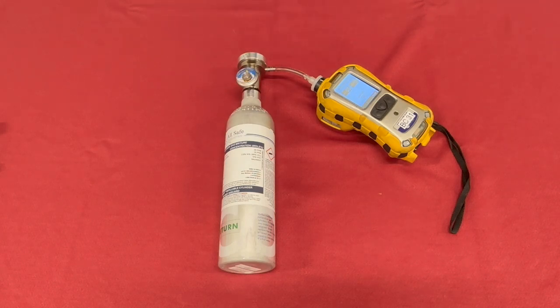Bump testing is not the same thing. All bump testing does is put the gas onto the meter, and once the meter is within 10% of the calibration gas, it says the sensors are working fine and I'm done, and it passes the sensor. If for some reason the sensor has drifted farther than 10% away from the calibration gas, it will fail the sensor. If you fail a sensor during a bump test, you should go back and try to do a calibration. These sensors drift over time. As they get older, they start to drift a little farther, a little faster. Some of our sensors, we don't replace until they actually go bad. Some of them are 3 or 4 years old, and as they get farther away from that new manufacturer date, they drift farther and quicker than they did in the first month.